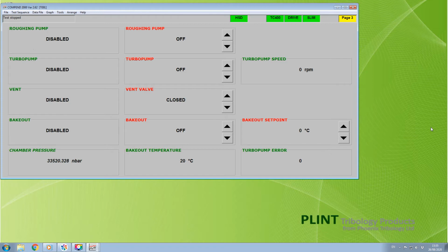Bakeout activates the halogen lamps in the chamber to raise the temperature of the internal surfaces to a preset maximum level. The default value is 80 centigrade. This aids desorption of volatile materials and is a necessary precondition for achieving ultra-high vacuum. Heating will not activate if the turbomolecular pump rotor speed is below 48,000 RPM.